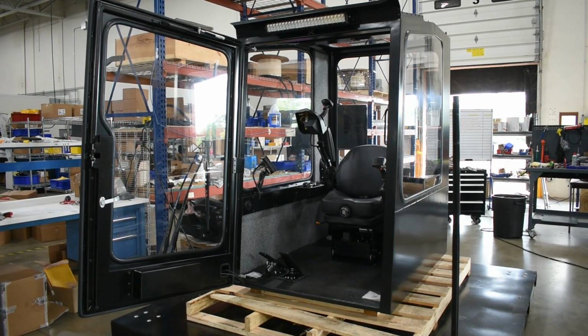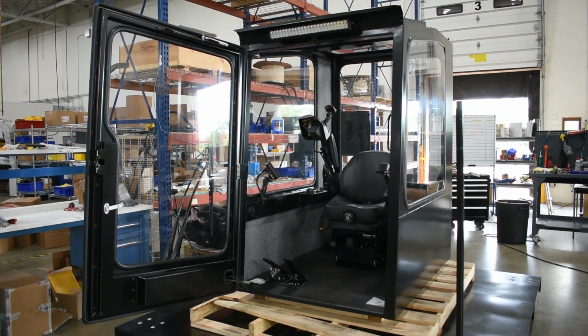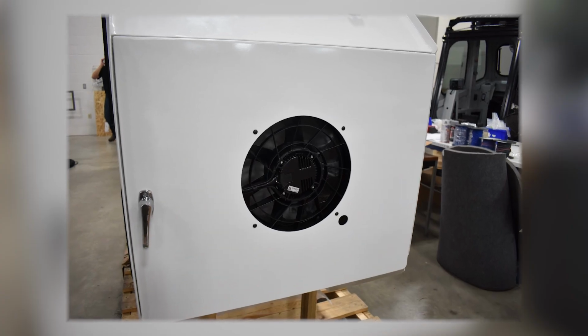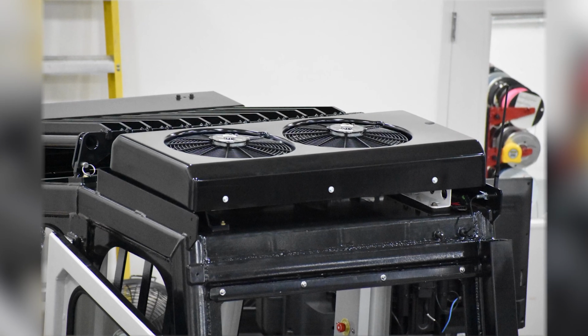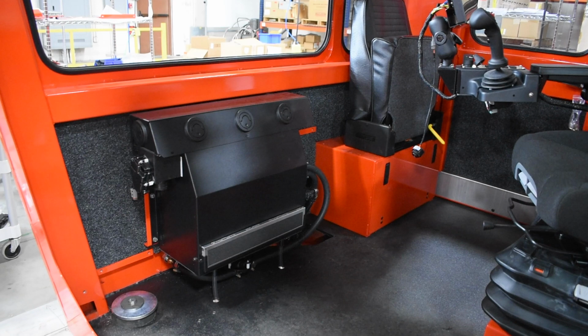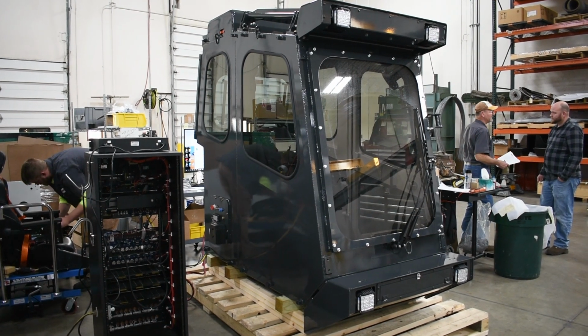So you need to know where your heat loads are, whether it's from the engine or from the sun, or if you're in a building, if it's a heated building, you'll need to figure out what insulation you need from it, what sort of glass area you have, and then compensate with the air conditioner heater, the size of it. Like some of these cabs are going into Arizona or New Mexico where they're 120 degrees. If you have specifically a dark cab, your cabs can be upwards of 120 degrees. So you need to cool them down to 75 or so.